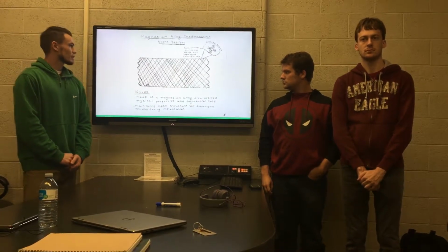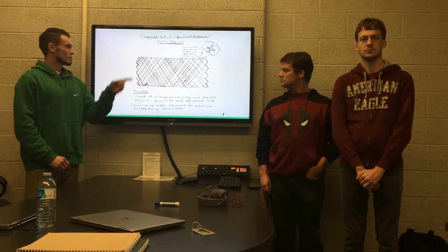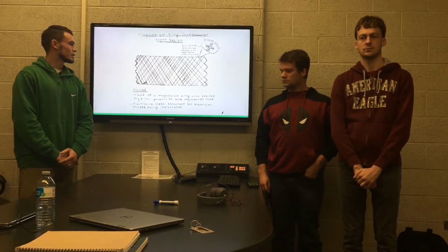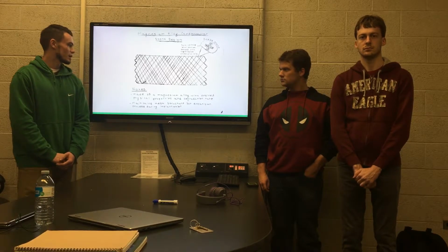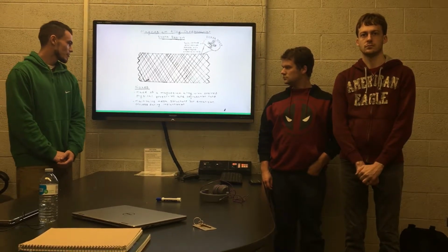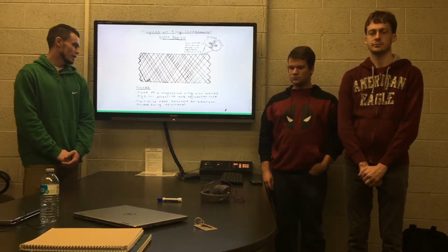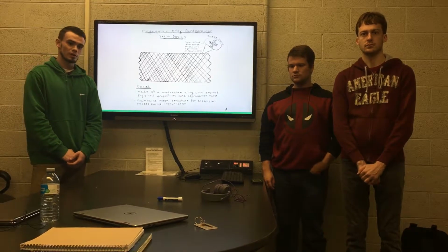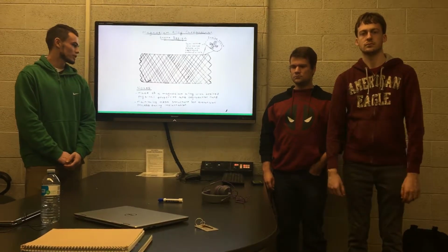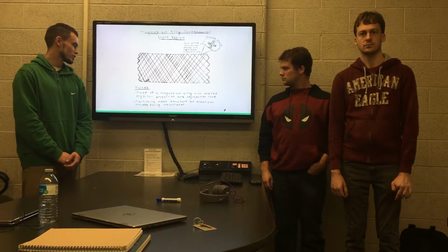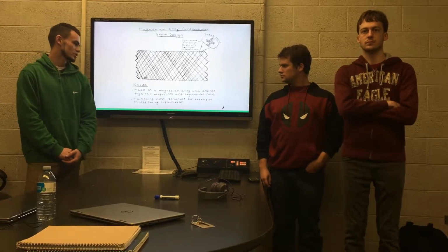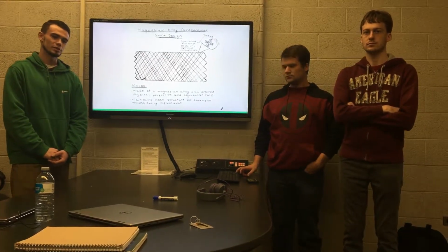So this just depicts our design with a semi-porous interior and autologously sourced endothelial cells implanted there. The magnesium alloy will have the desired degradation rate to allow an optimum ratio of tissue growth to degradation of our stent, and it maintains the mesh structure for expansion during implantation.